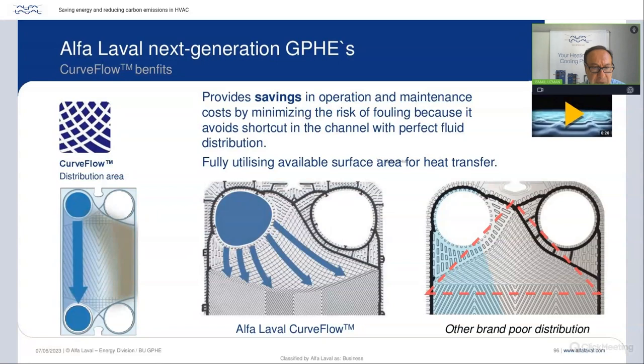So how does Alfa Laval achieve this? You see this distribution pattern here, what Alfa Laval does with the curve flow, you see that there is a curve here. This is a short distance, and the fluid, the water would like to go in this short distance, which is usually low resistance to flow. But if Alfa Laval makes the resistance to flow along this short distance equal to that of this longer distance where usually water doesn't want to go, then equal resistance all along this area means that we will make sure that the fluid does go to these extremities. And if it is not like this one, in a non-Alfa Laval distribution pattern, you will see that at part load, for example, the fluid will only travel part of the plate surface.